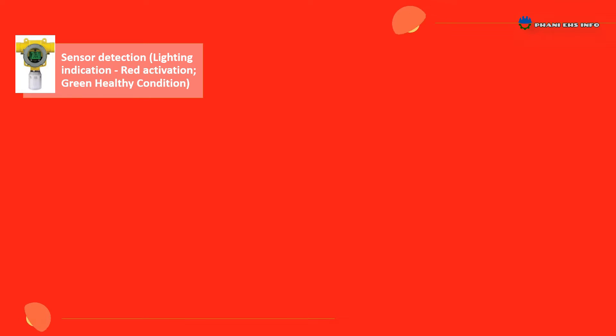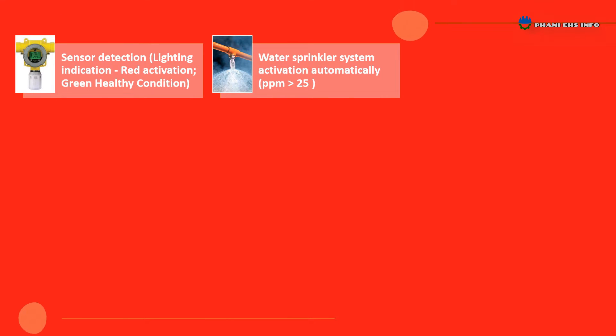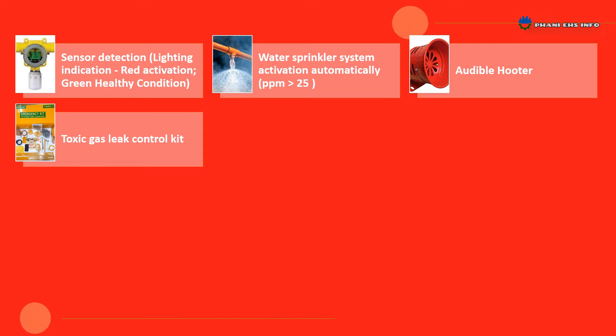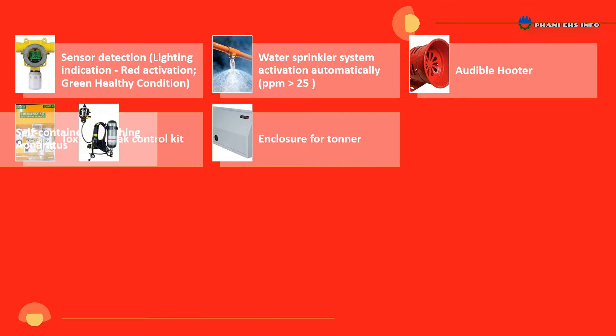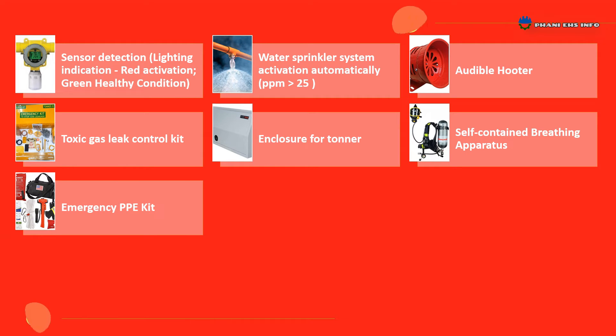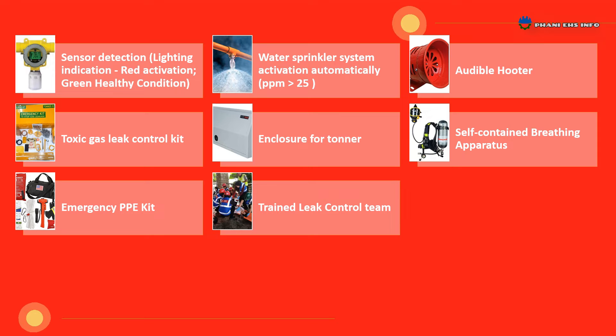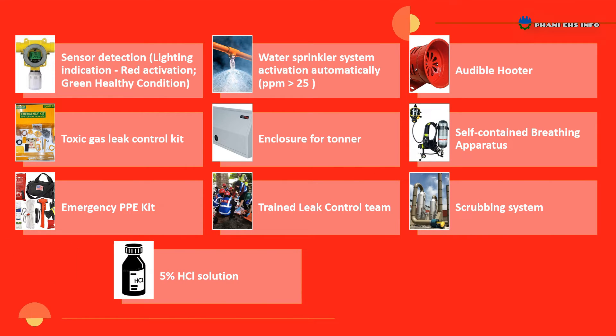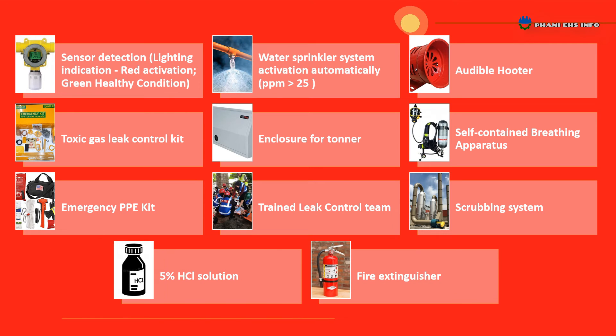Emergency systems include: sensor detection with lighting indication — red for activation, green for healthy condition. Water sprinkler system activates automatically at 25 ppm. Audible hooter. Toxic gas leak control kit. Enclosure for tonner. Self-contained breathing apparatus (SCBA). Emergency PPE kit. Trained leak control team. Scrubbing system. 5% HCl solution. Fire extinguisher.